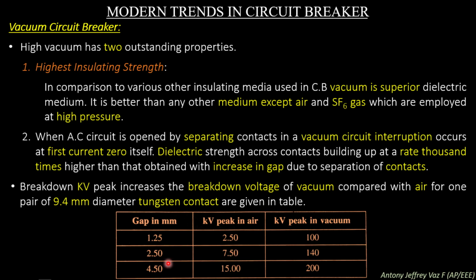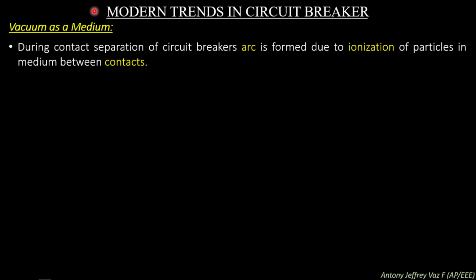So at the last stage you can see we can use 4.5 mm contact separation for 15 kilovolt peak in air. At the same time we can use 200 kilovolt peak in vacuum. So on comparison, the kilovolt peak in vacuum is very much higher, and it can be used with a minimum gap of 4.5 mm.